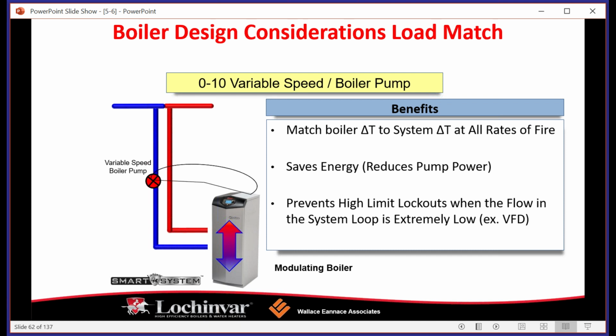But also, we want to reduce the amount of cycles on the equipment, okay? Because you don't want to just turn it on, off, because again, it's bad for the lifetime of the equipment. You don't need your igniters and your flame sensors and your fan motors and everything else getting worked 25, 50, 100 times a day, right? You want it to come on, you want it to run as long as it needs to maintain the required temperature, regardless of your method of input, and then turn itself off and put itself into standby. So that's for anti-cycling, that's for component lifespan, and that is for fuel efficiency. So there are a lot of benefits to doing it this way.